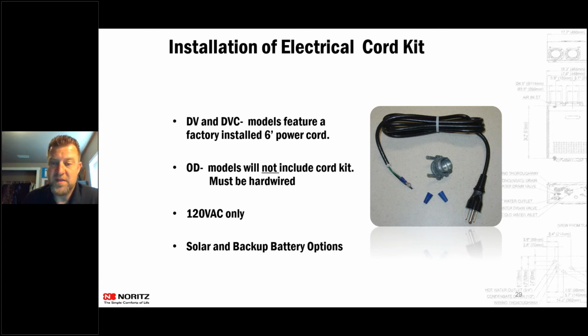We do recommend that if you need to run that cord longer than the 6 feet that is there, you get a high-grade cord. If you have to run it 12 feet, we don't recommend plugging into an extension cord and then running that extension cord out. We would ask that if you need to run it 12 feet, get a 12-foot extension cord, cut the end off of it, and wire it directly to the unit and run that cord straight off. We don't want that point in between.